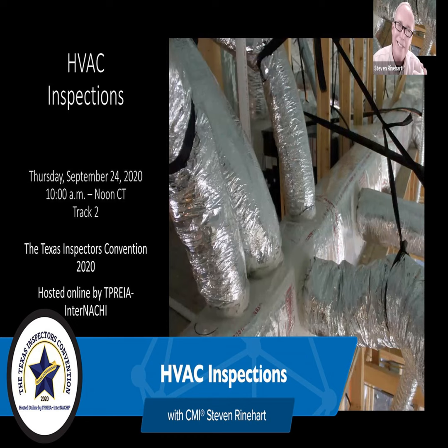There have been times where a duct has been pulled off. You look up through the register and you can see the roof duct. But you're looking for an absence of flow. Most often, it's a restriction in the attic. Somebody's rooted through the attic. They had them suspended, maybe one of the ties fell, and now it's got a restriction like a tourniquet from the other joints because of the sag.